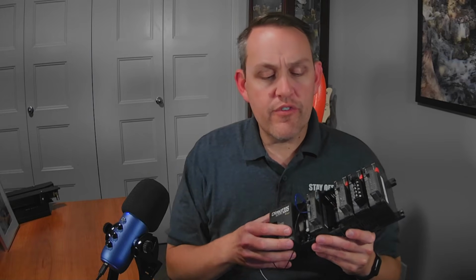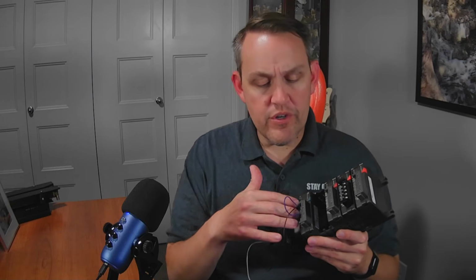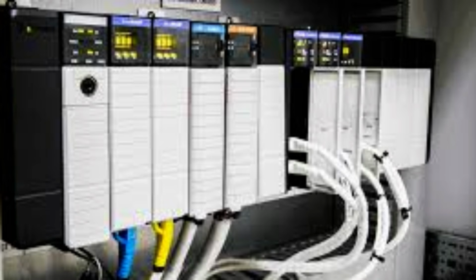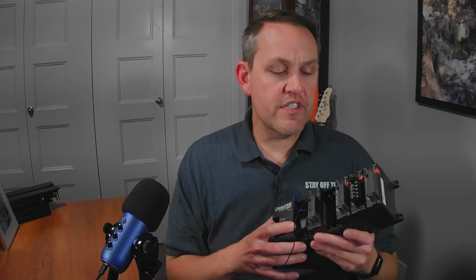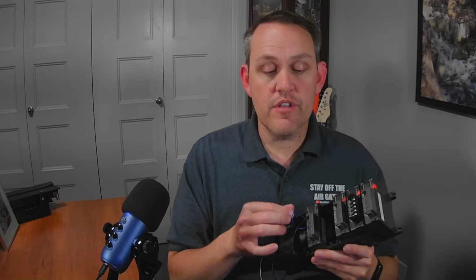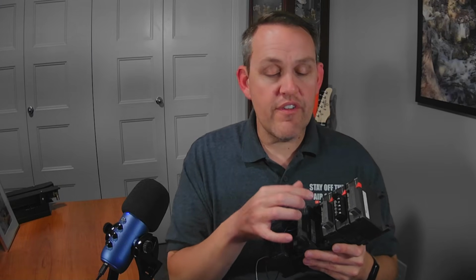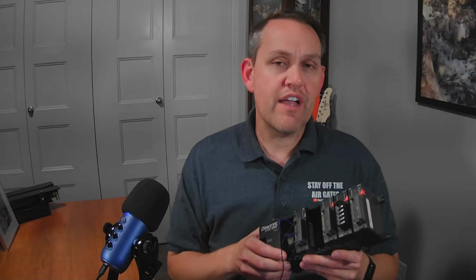In general, when it comes to the size of inputs and outputs, a lot of cards have 16 inputs or 16 outputs. That's not a universal standard, but a lot had that. So you'd see these little points on here going up to 16 on both sides. Newer modules on newer PLCs have gotten smaller and smaller, and so have the outputs and inputs to them. Now a lot of the newer PLCs actually have inputs and outputs on the same cards. Those cards only have about 4 or 8 points on them, but the cards have much more capability than the older stuff originally had.